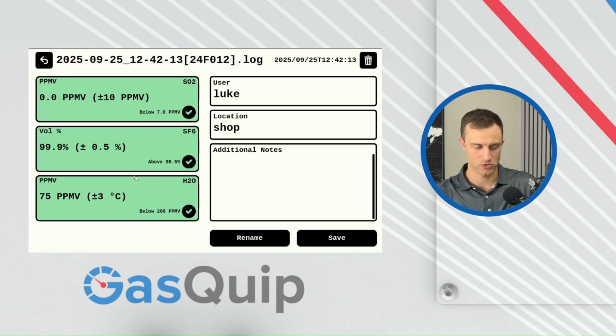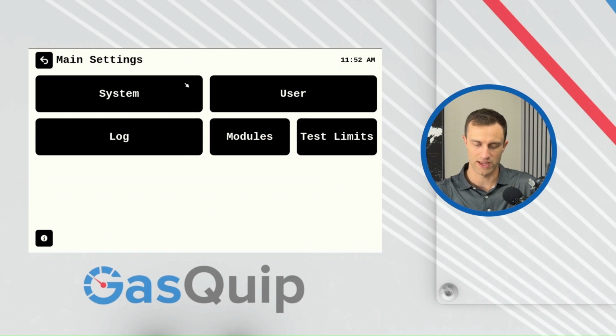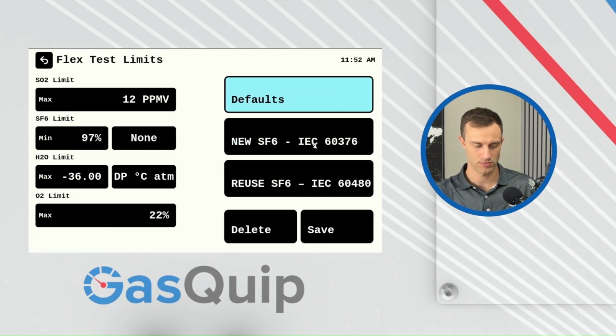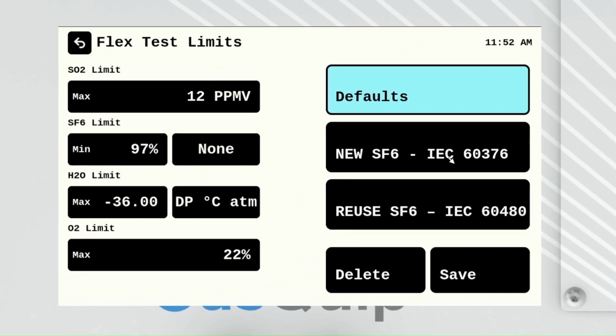So if we go back to our settings by going to the main settings and going to test limits, let me blow this up again, we can see that we have some defaulted values here for each of the individual sensors. So like, for example, here we have a max test limit for SO2 because we don't need a minimum amount because that's a contaminant. So we have a max of 12 ppmv, and that is a default that we send with the unit.